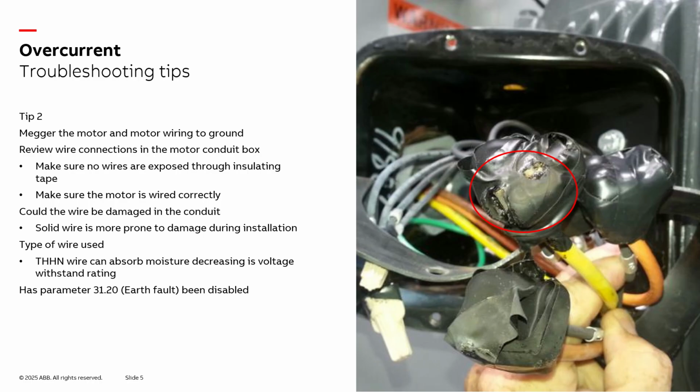There's no copper, for example, poking through the electrical tape. I've seen that also before, a copper wire strand poked through the electrical tape in the motor conduit box and arced to the motor frame.